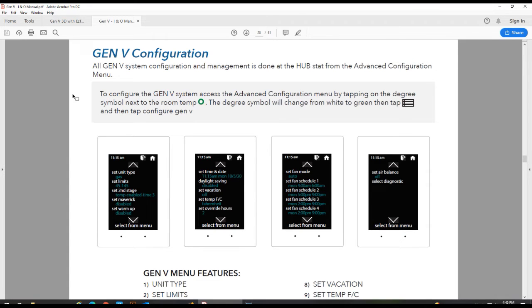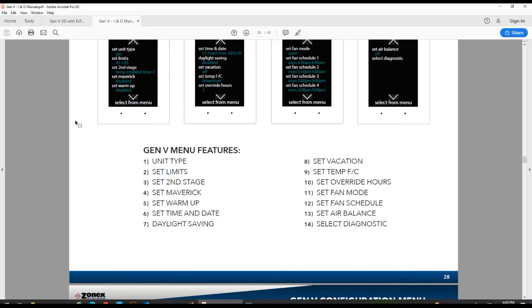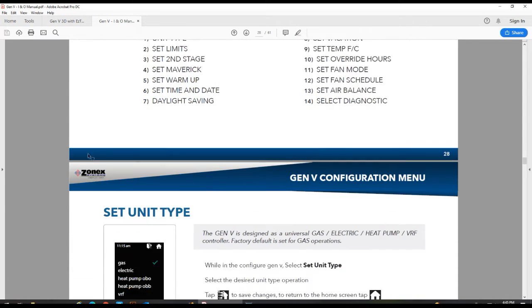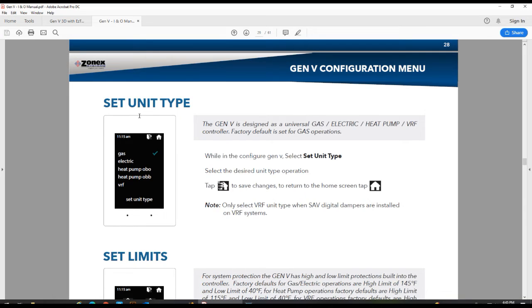There are a number of different features and functions that are offered via the Gen V controller. So from your hub thermostat, you're going to go ahead and select Configure Gen V. And we're going to just scroll through each one individually and make the changes according to the operation you would expect. So setting our unit type, we offer 5 different unit type functions. So gas, electric operation, heat pump, O or B operation, and then VRF. So go ahead and select the proper operation that you would expect for your system.